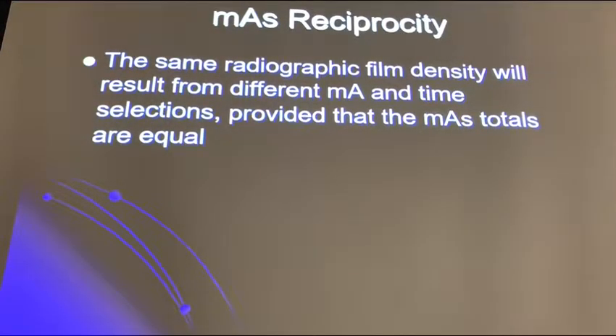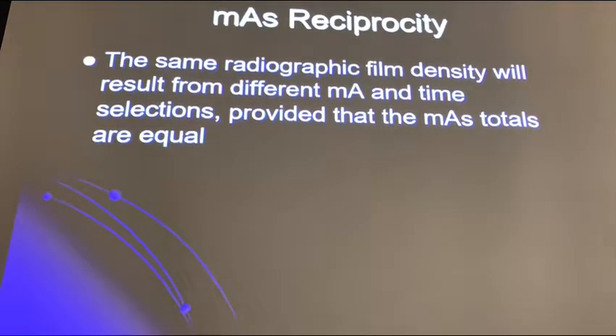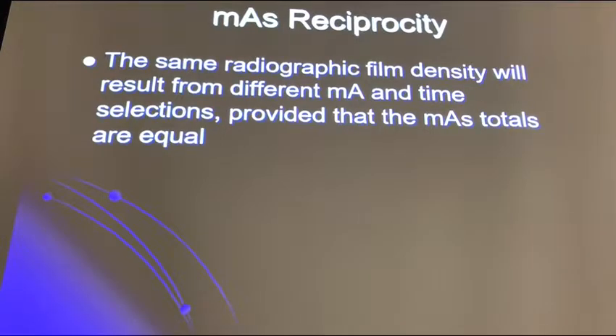MAS reciprocity: the same radiographic film density — or exposure, for computerized systems — will result from different MA and time selections, provided the MAS totals are equal. It doesn't matter what combination of time and MA you use; if the end result is the same MAS, you should have the same exposure, with some small variability.